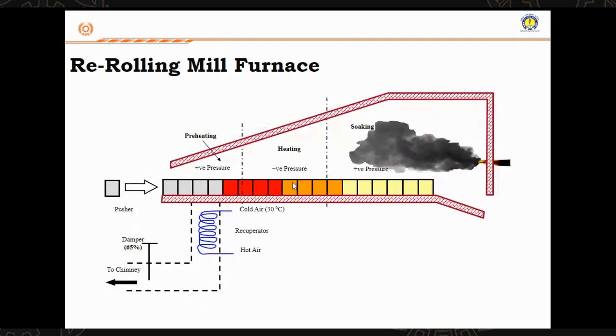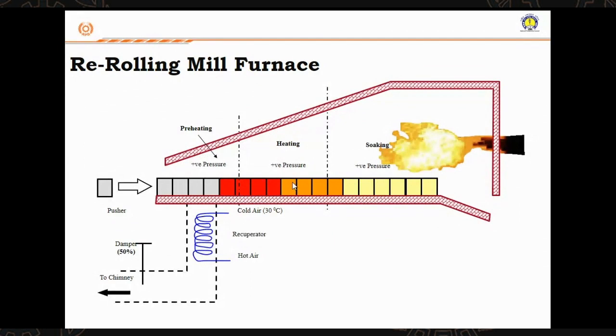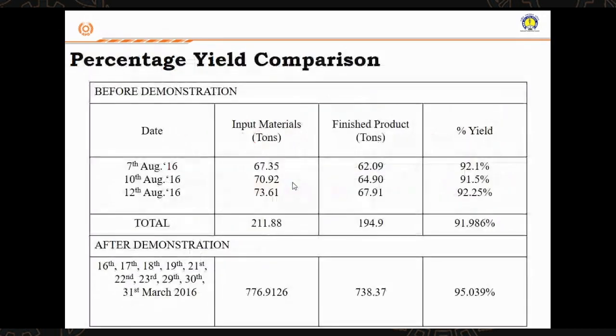So further, if you go below 50, if you still reduce the damper opening by around 65%, it affects the combustion itself. So we have tried to estimate the level of damper operation for the operator. And we have conducted this study, and you can just see the yield change from 91.86 percent to 95 percent. So the yield improvement means more production is coming out from the furnace, because there is no outside air going inside, and the combustion is proper because of the efficient burner technology.